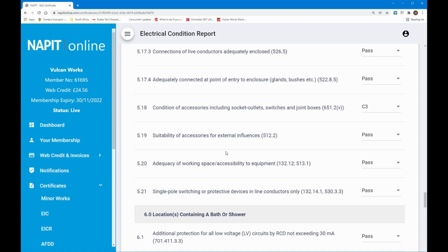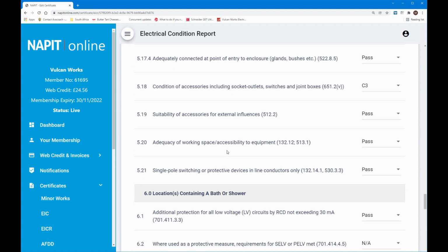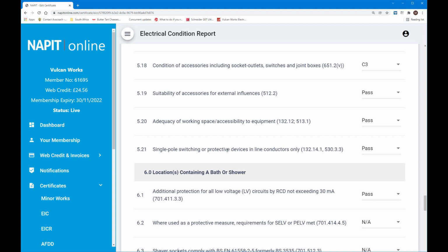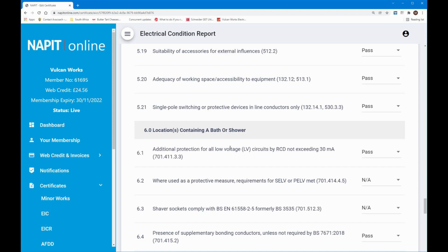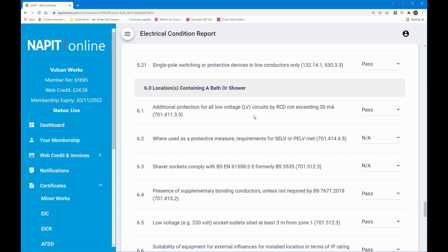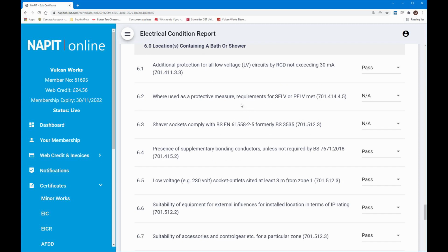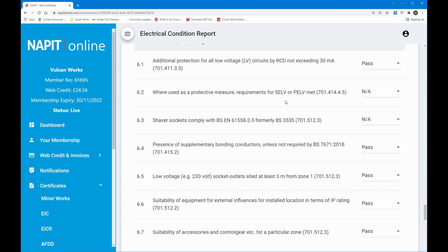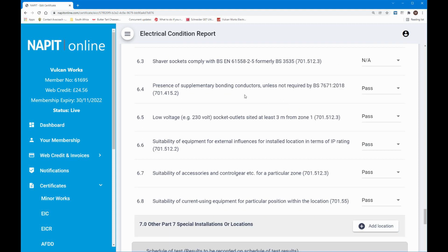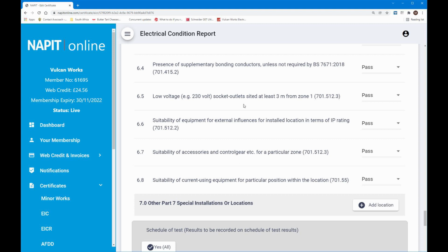That's fine. Adequate working space, yeah, no worries there. Single pole switching, yeah, that's fine, no problem there either. So up in the bath and the showers, yep, that's fine, that was okay. There were no SELV or PELV, so it's not applicable. There were no shaver sockets, so that's not applicable. There was supplementary bonding in the bathrooms, so that passed. Low voltage socket outlets, there were no socket outlets at all in anything, so I've passed it. I could have put down not applicable, but I've passed it.